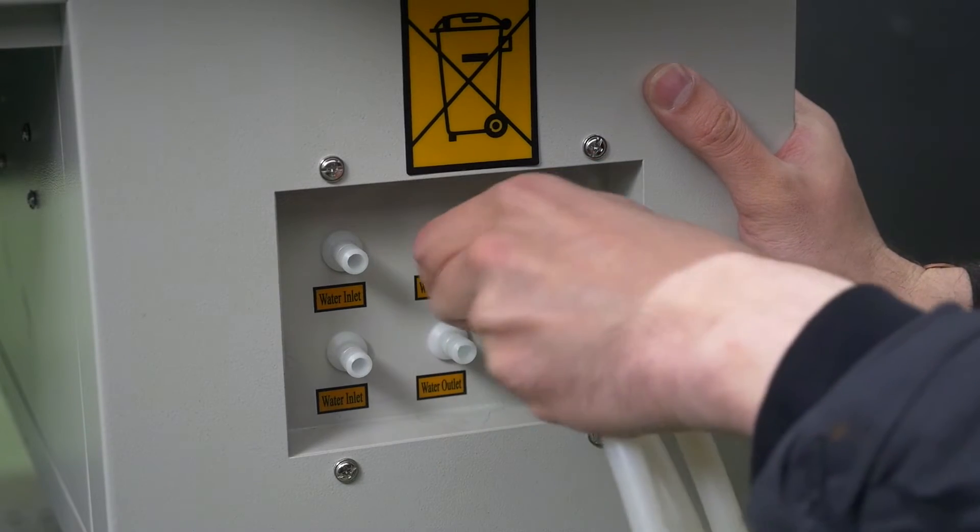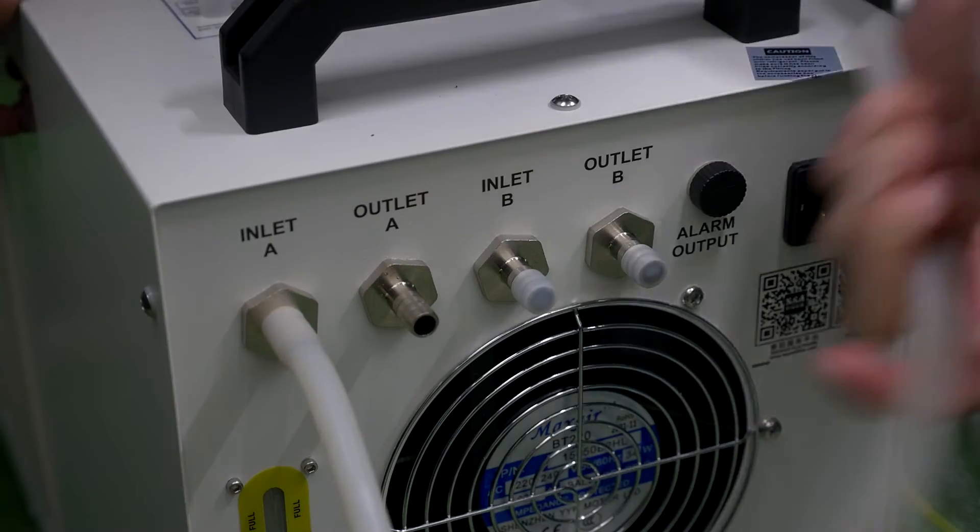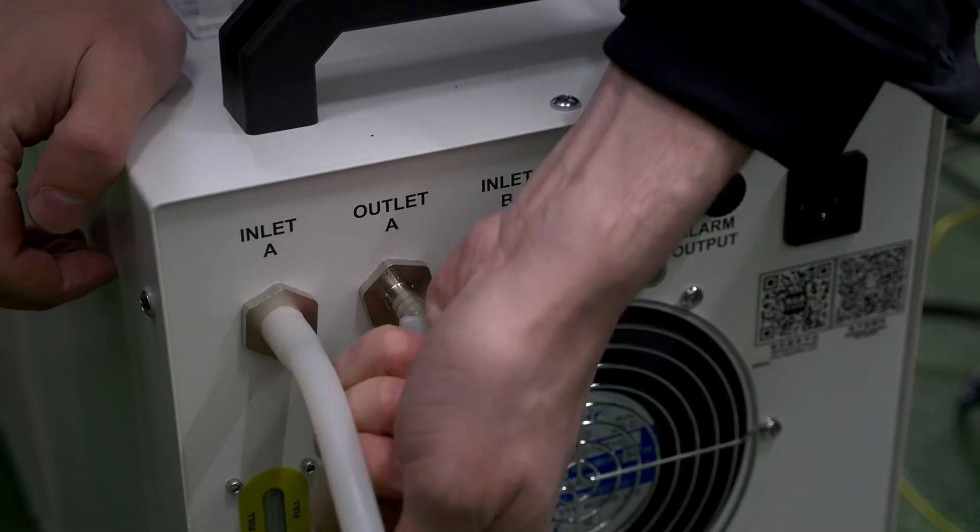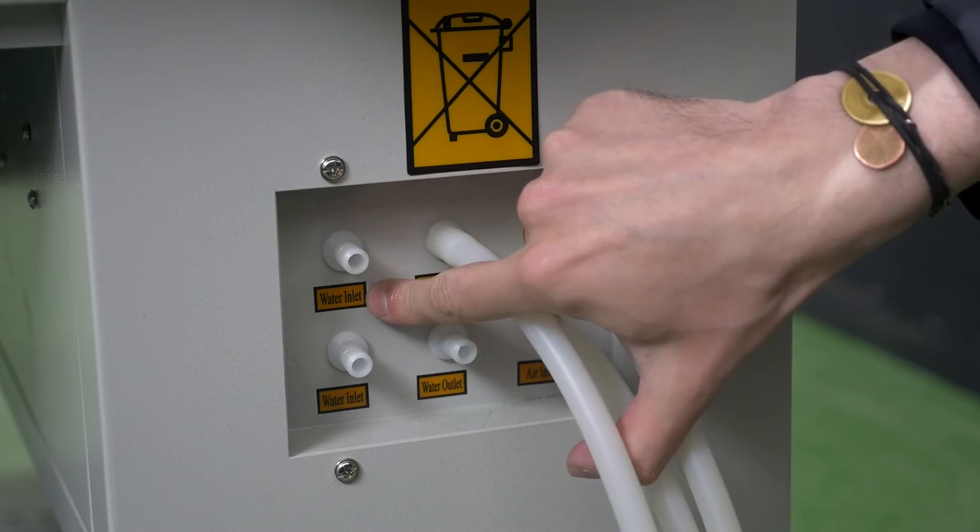Connect the second end of the silicone hoses to the chiller in the following order. Connect the hose from the chiller water inlet fitting to the water outlet on the machine, and the hose from the chiller water outlet fitting to the water inlet on the machine.